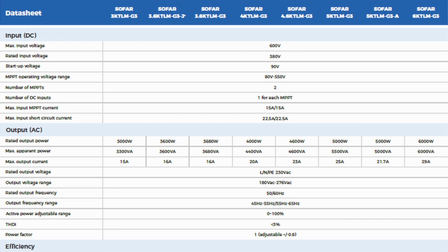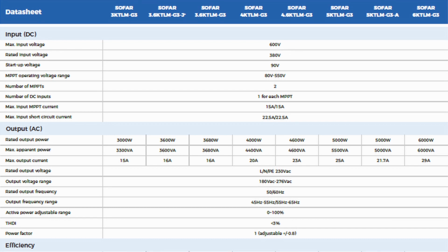Basically, all inverters have safety parameters that you can't cross, and inverters are always going to synchronize to the grid, so if the grid goes high, the inverter voltage goes high as well. This is just the frequency, 50-60 Hertz. Output range between 45 and 55, 55 to 65, variable across different countries and different safety parameters. Active power adjustable range between 0 and 100%, so that means you can limit the inverter, let's say, to 50% export. Total harmonic distortion less than 3%. Power factor 1, adjustable plus minus down to 0.8.